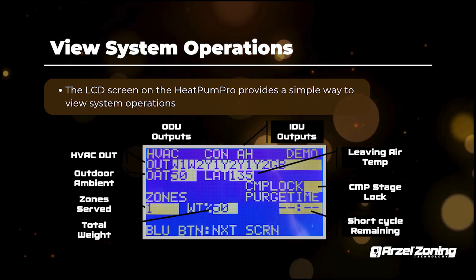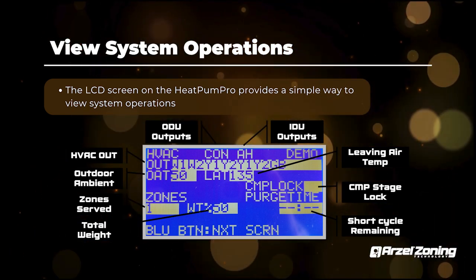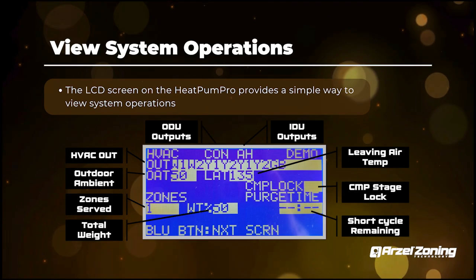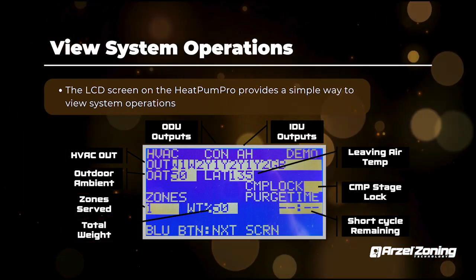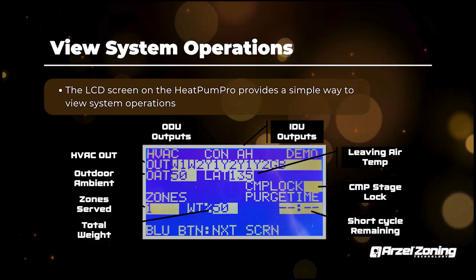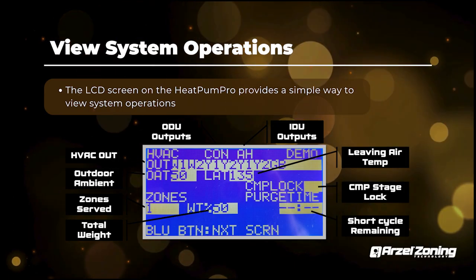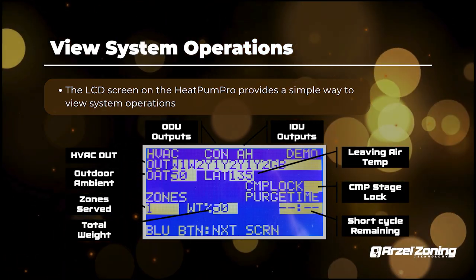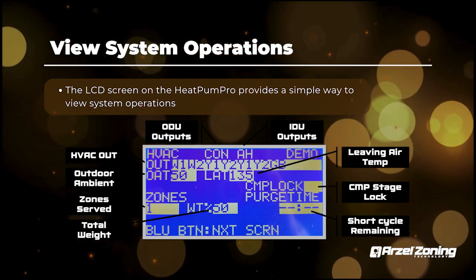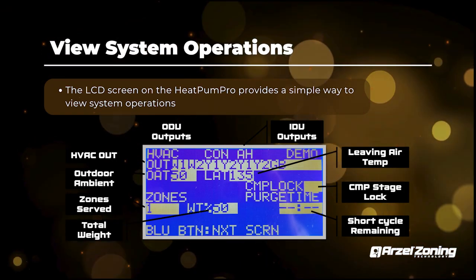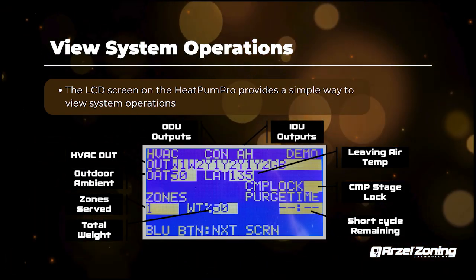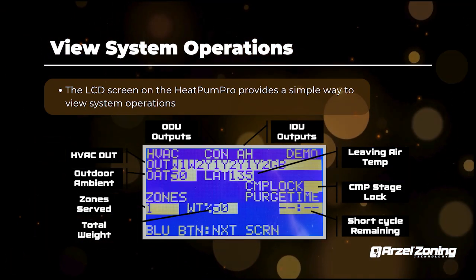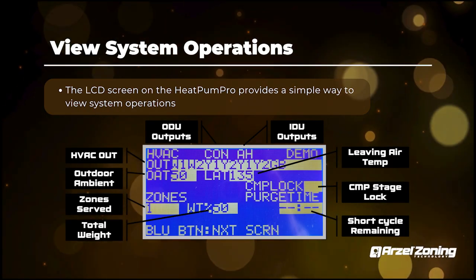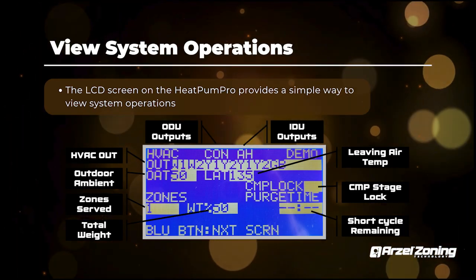And then everything else on that line is just going to be air handler or furnace. So W1, W2 will show up there. Your G, your B, or your O will also show up on that line. So anything that we energize, it'll show up right there and you guys can tell exactly what we're outputting to your equipment. Right underneath that, you're going to have your OAT and LAT. OAT is outdoor air temperature, so that's what we're reading outside. LAT is your leaving air temperature, so that's going to be our leaving air in your supply plenum.